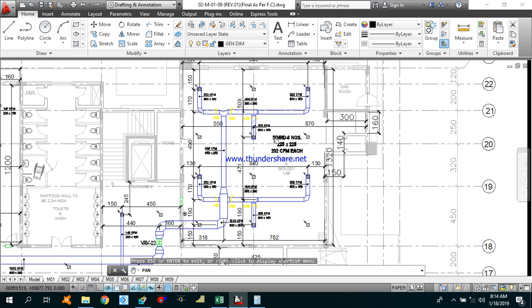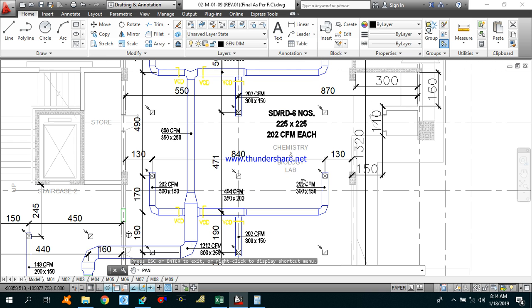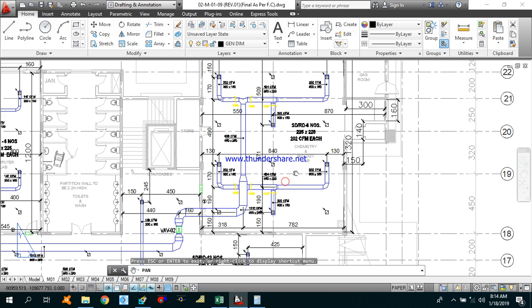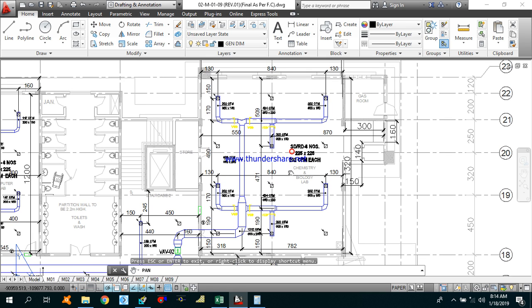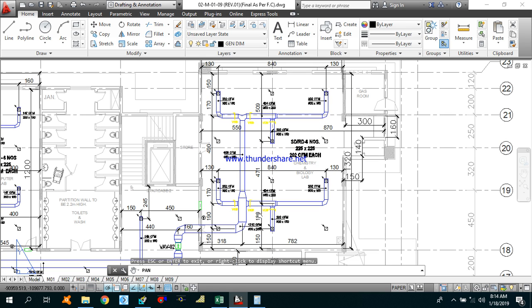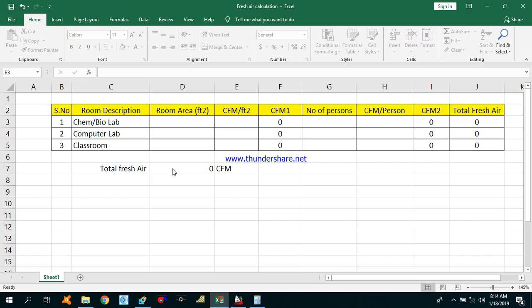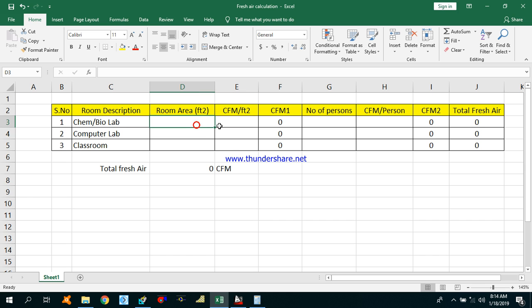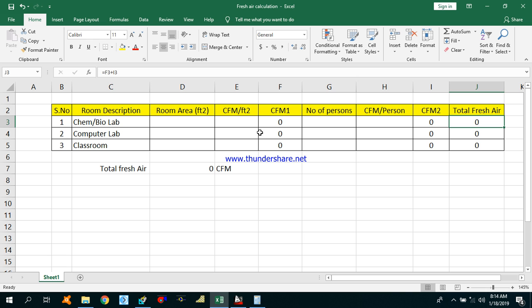First I will calculate the Fresh Air CFM for this chemistry and bio lab. In order to calculate the Fresh Air CFM, I have made this Excel sheet. What we need here is the room area, CFM per square feet, number of persons, and CFM per person. The total Fresh Air will be the sum of CFM1 plus CFM2.